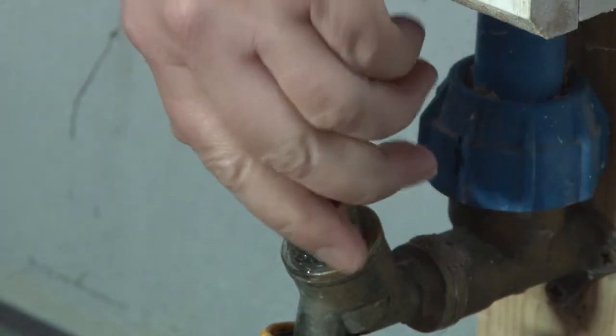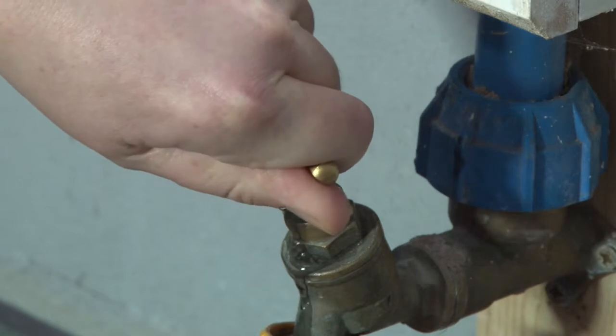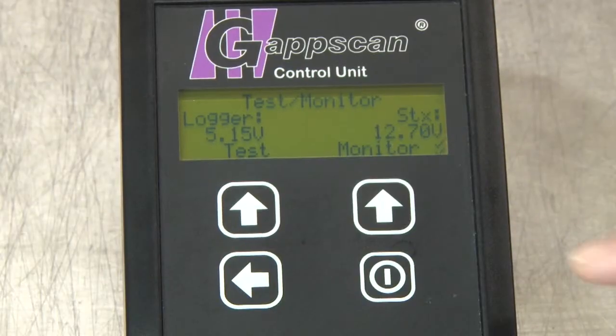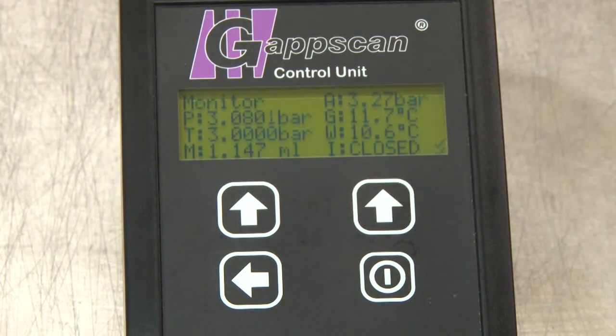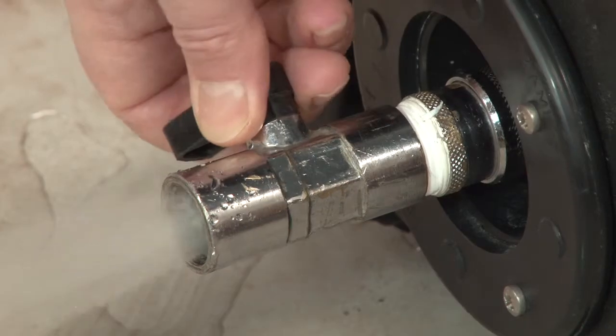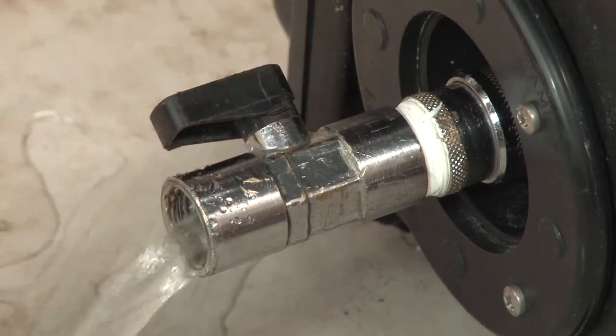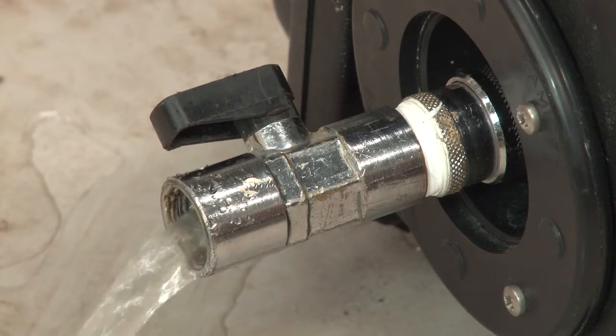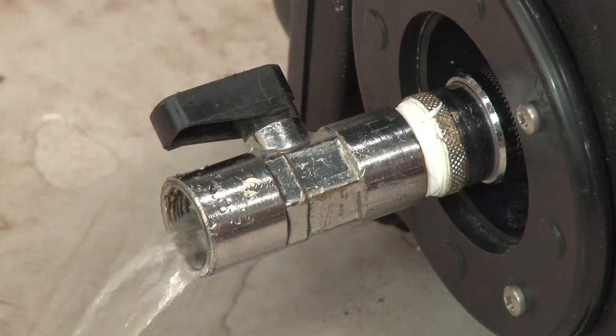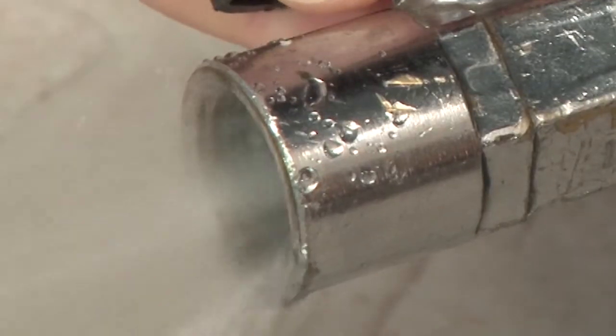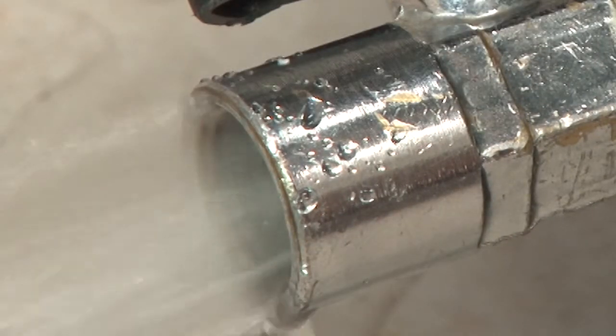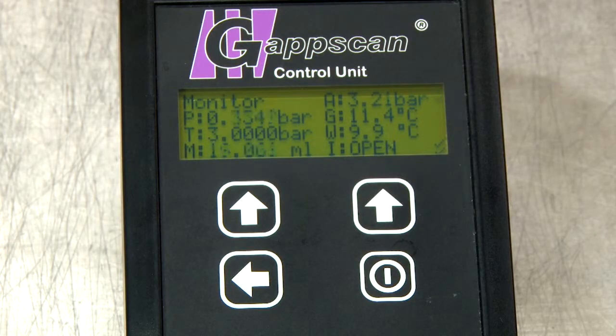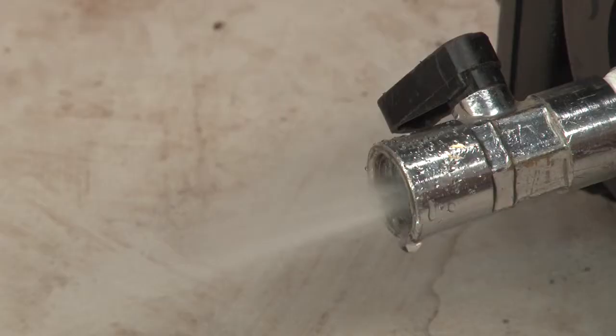Fill the unit with water from the mains tap. Put the control unit in monitor mode by selecting Mon Test, then Monitor. Open the stop valve to allow the water to flow through the unit for about 1 minute. On the control unit, you will see the pressure dropping. Open and close the stop valve to extract any air from the unit.